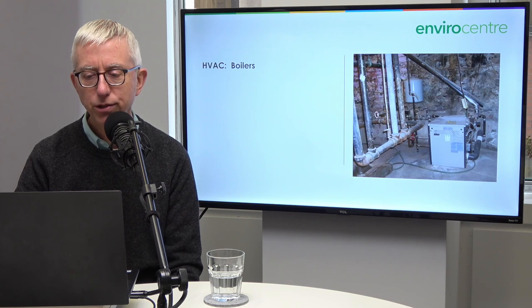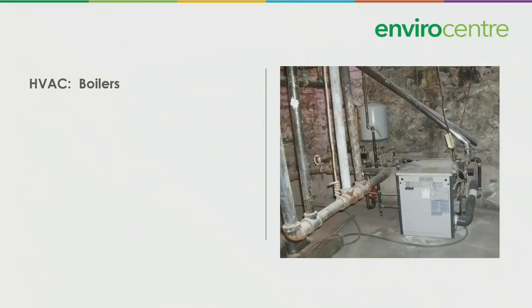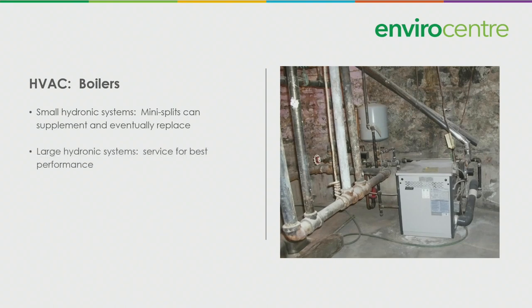If you've got a boiler system, here's a boiler system for an older building. It's about 200,000 BTU. If you have a small hydronic system, and I kind of suggest that this is in that category, you can add mini split air source heat pumps to supplement and eventually replace your boiler system. With multiple indoor heads, mini splits can provide better comfort control.